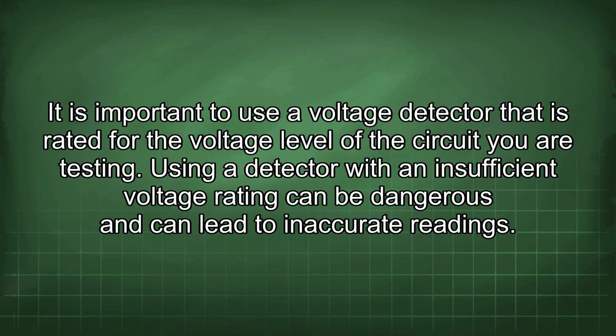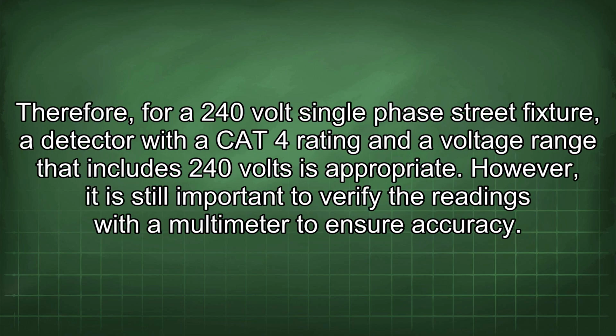It is important to use a voltage detector that is rated for the voltage level of the circuit you are testing. Using a detector with an insufficient voltage rating can be dangerous and can lead to inaccurate readings. Therefore, for a 240-volt single-phase street fixture, a detector with a CAT4 rating and a voltage range that includes 240 volts is appropriate. However, it is still important to verify the readings with a multimeter to ensure accuracy.